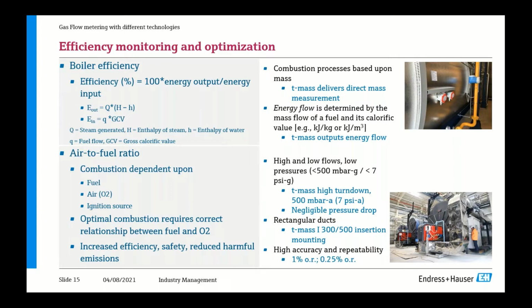The thermal mass technology is very flexible and versatile, which allows it to be used in a mixture of applications. However, very frequently, because it's also ideally suited for this purpose, and as Oliver also indicated, it's used in utility type applications very often. My focus today is a particular utility application dealing with natural gas, and natural gas used in combustion type applications. I'm looking specifically at combustion gas for boilers.